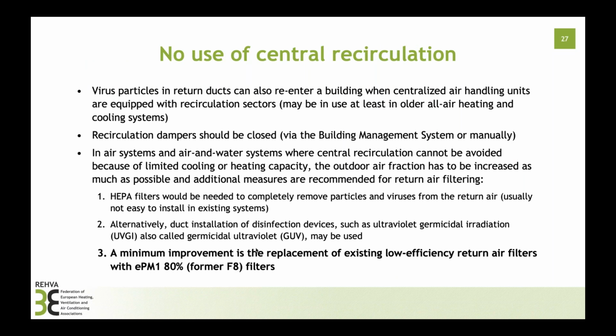So that's perhaps a very important guidance that applies all over Europe, because these rotary heat exchangers are very, very popular equipment in all public buildings, office buildings, and so on. But then the next issue is recirculation, and generally, indeed, it is recommended that in epidemic conditions, recirculation should not be used. So if possible, close the recirculation damper. Sometimes this needs to be done manually, sometimes it can be done from the BMS.